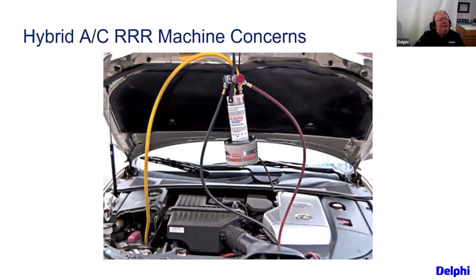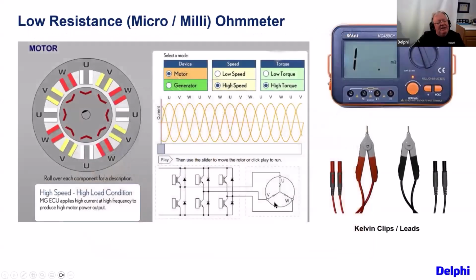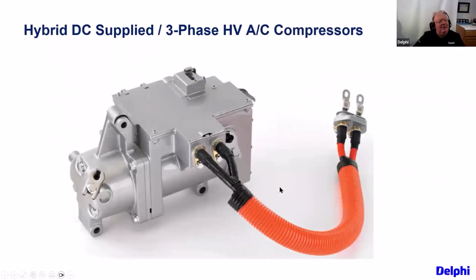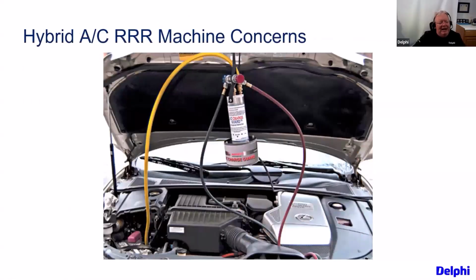This is a tool used because these compressor windings can have some oil from the refrigerant move past them. This was a great idea from Aircept, so you didn't have to have two RRR machines, because Toyota and some other manufacturers said they don't want their electric compressor vehicles exposed to the same oils used in a lot of 134A cars, mainly PAG oil. Tag oil is hygroscopic - it absorbs moisture. And Toyota, Honda, and some others said they don't want that kind of cross contamination going on.